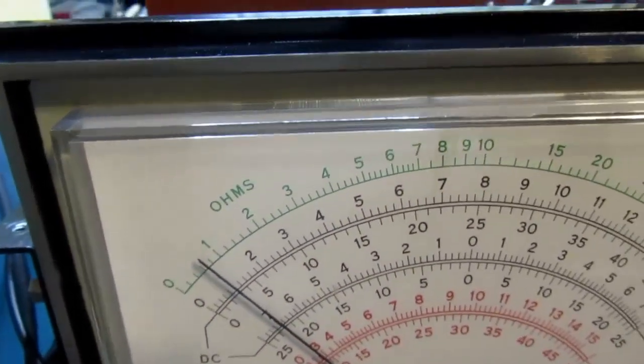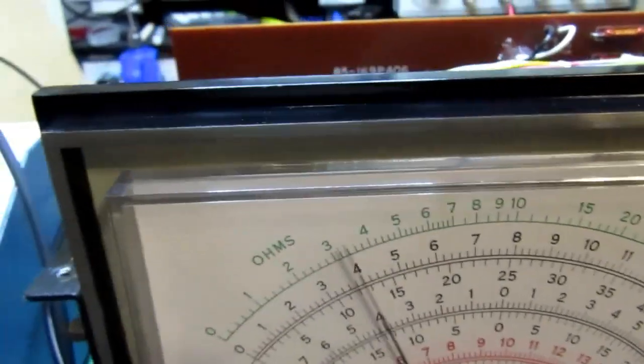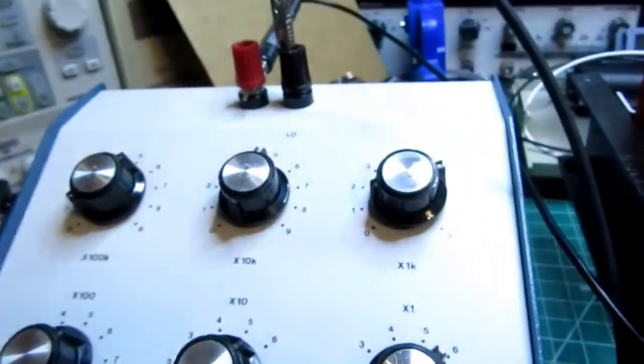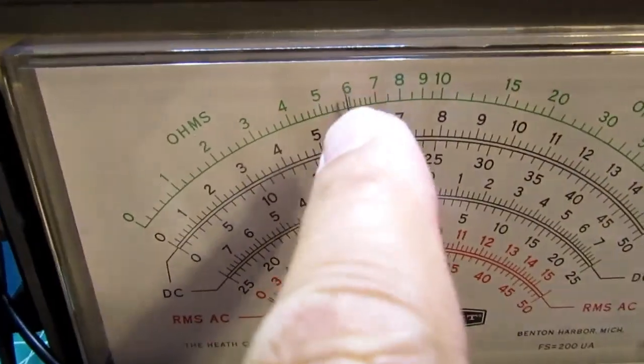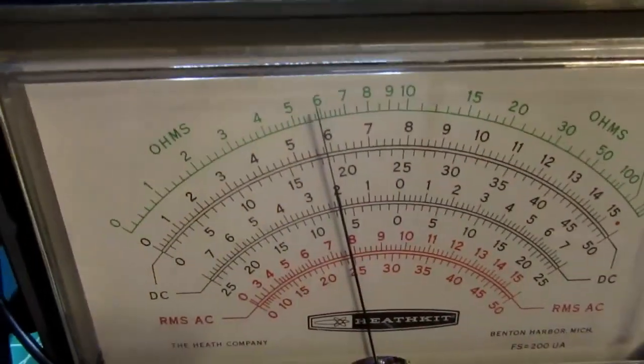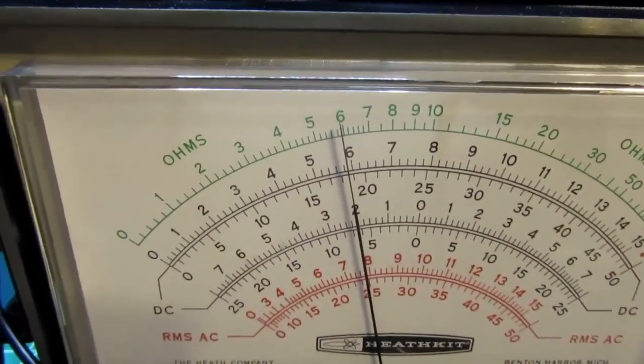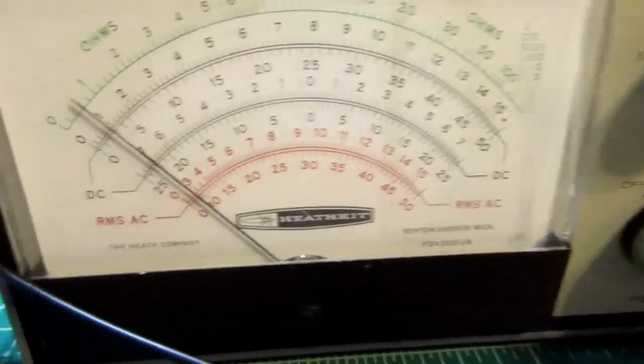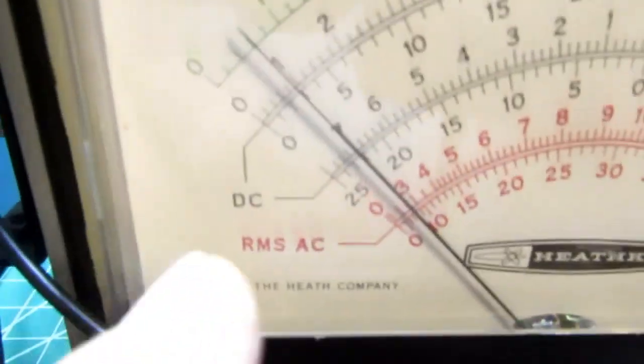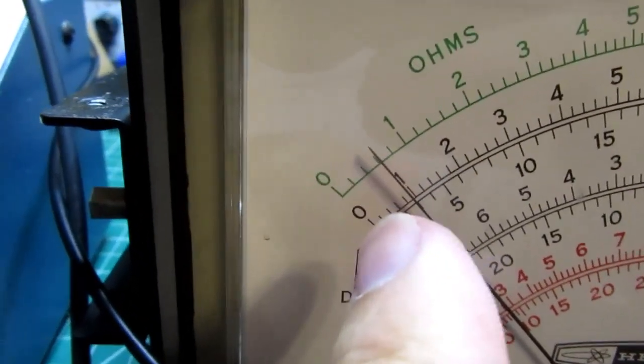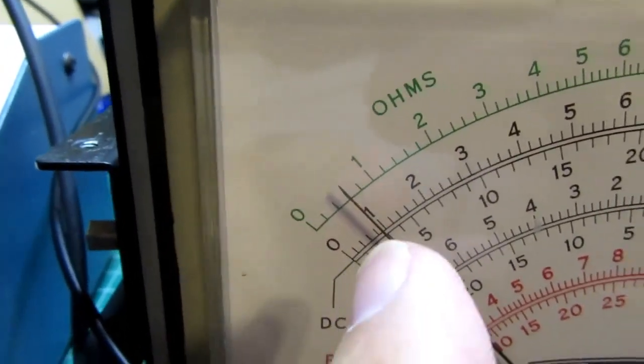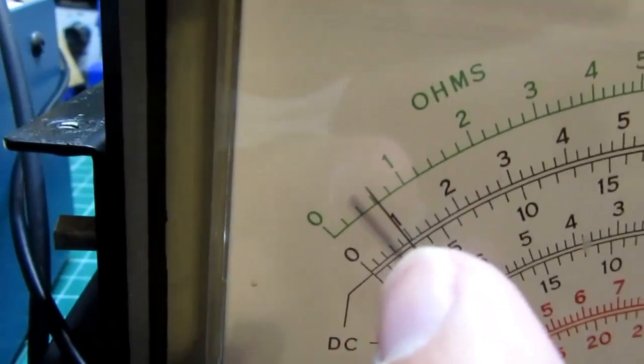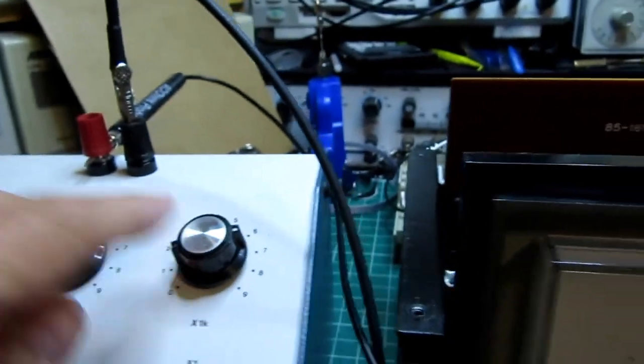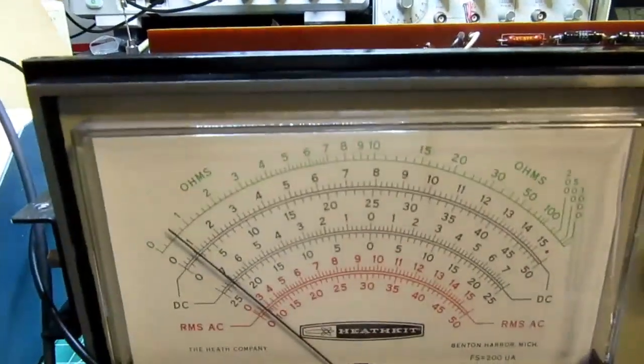And let's bring it up to 57K, and it's a little high towards 6 on there, but if I go up to the 100K, it's reading about 6, a little higher than 6, and that's appropriate for 56. So again, it's really close.